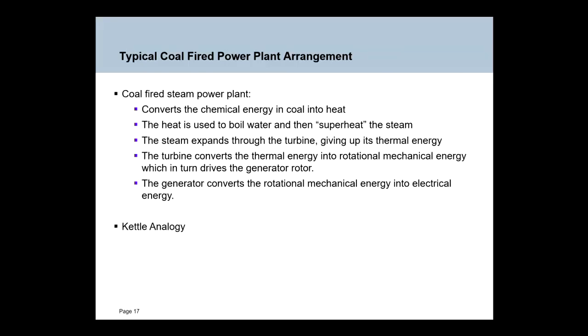Okay, so what do we do in a coal-fired power station? We take coal, which is carbon and other chemicals. We burn that coal, we give off heat, we use that heat to boil water and then superheat the water to produce superheated steam. We then expand that superheated steam through a turbine. The thermal energy is converted into rotational mechanical energy. That rotational mechanical energy in the turbine turns a generator which produces electricity which is transmitted to the grid.